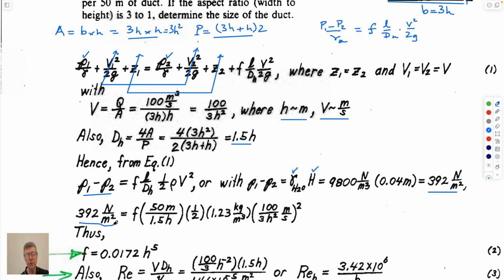So we know that the pressure drop in terms of the correct magnitude is a function of friction factor, length over diameter, density of air times V squared. If we put those terms in: 50 meters long duct, the hydraulic diameter is 1.5h, the term here is a half, the density of air is 1 kilogram per cubic meter, as we use, or 1.23 in this case. And the V squared term is from this - it's 100 over 3h squared here.